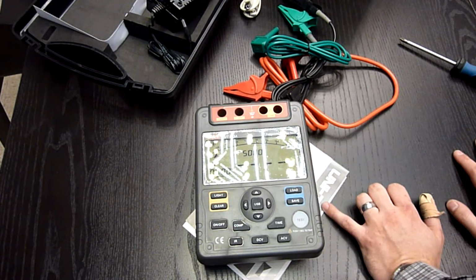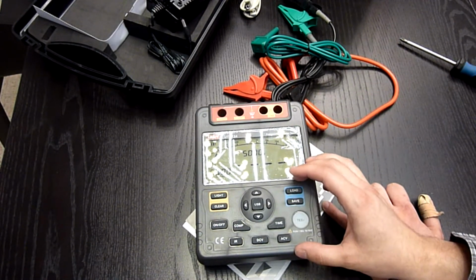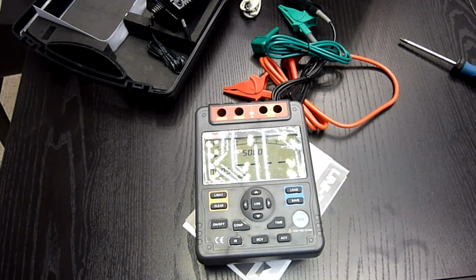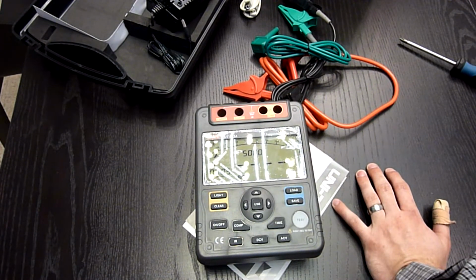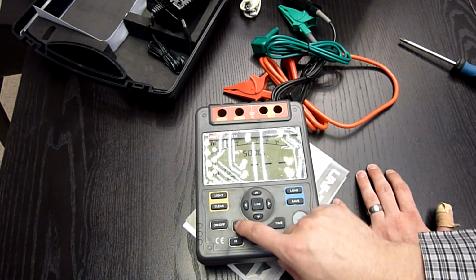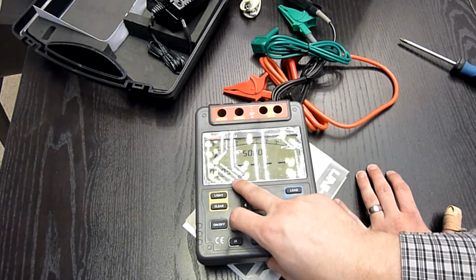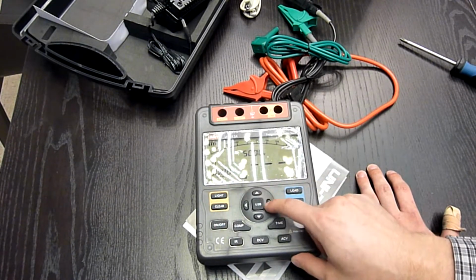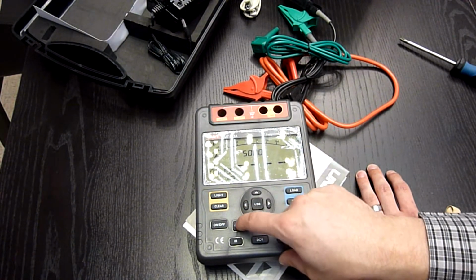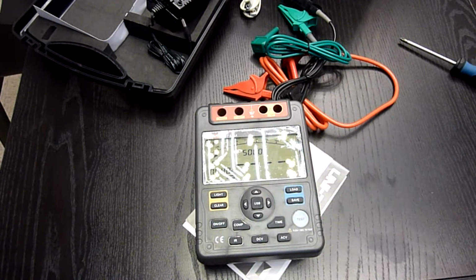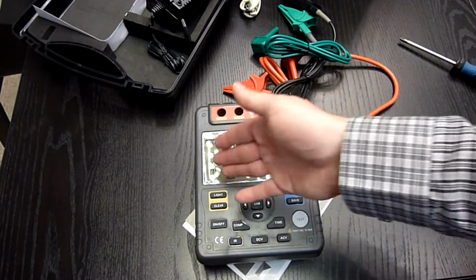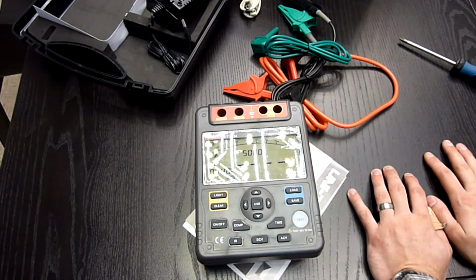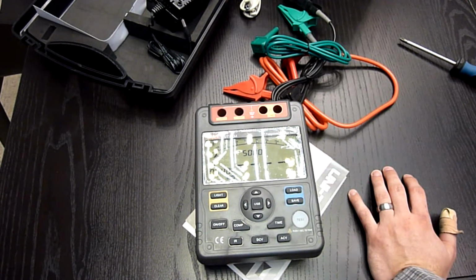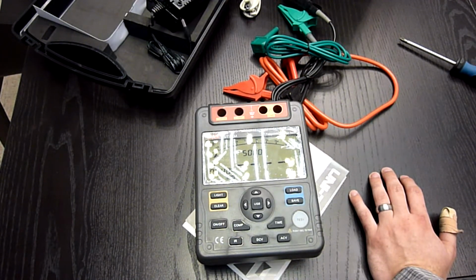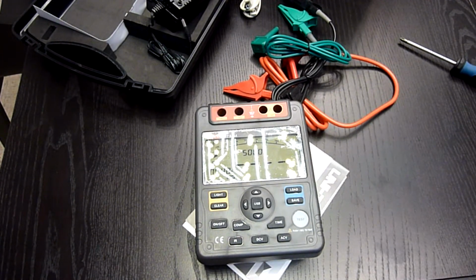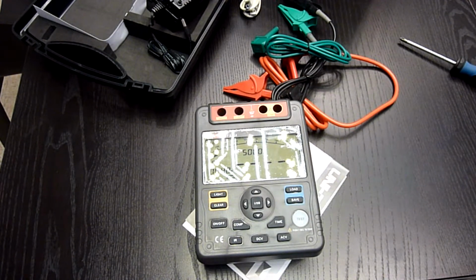And very interesting is that this device also has timers. Because if you set timers, you can do other types of measurement. You can do comparison measurements when you have preset values, 10 megaohms for 5 seconds. You can choose the time. You can also change the value, 20 megaohms, 30. And it will measure for the period of time you put in and compare if your value is higher or lower than this. Besides that, it can measure polarization index, PI, and dielectric absorption, DAR. So it's a pretty handy device.